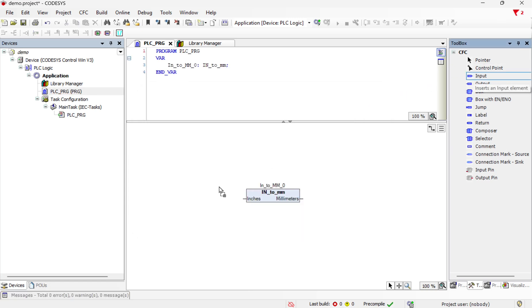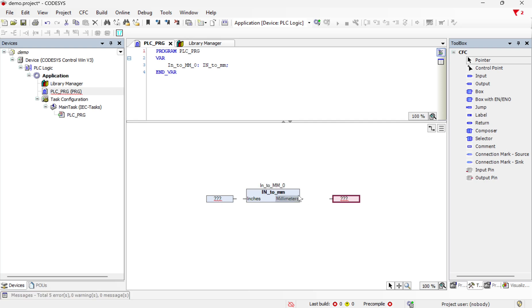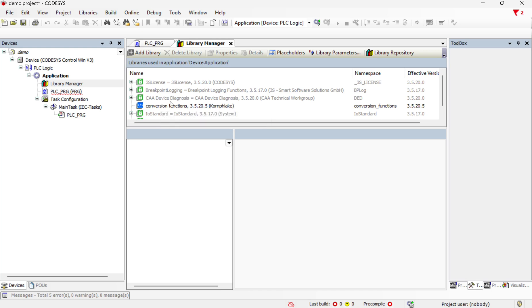So then I can bring in my input and my output and I can connect those and assign variables for the input and output. And I can call as many of these as I need to and in as many POUs as I need to. And this function block will be in that common repository or the common library and I can use that in any other program as long as I add it to the library manager for the specific project.